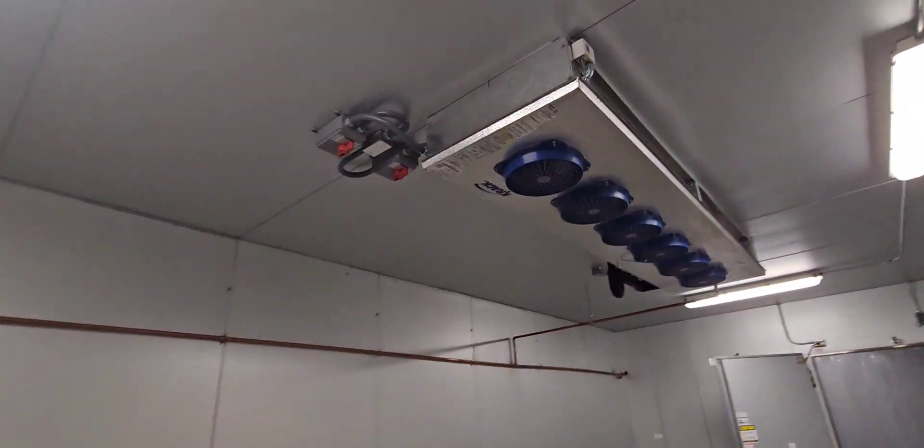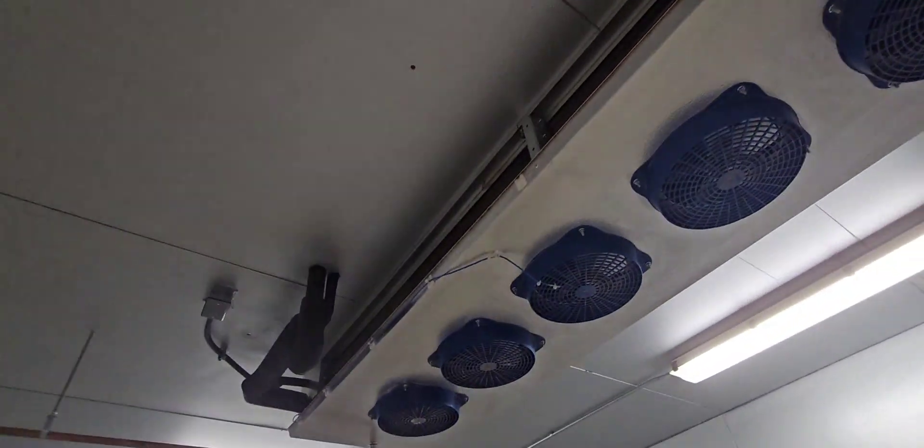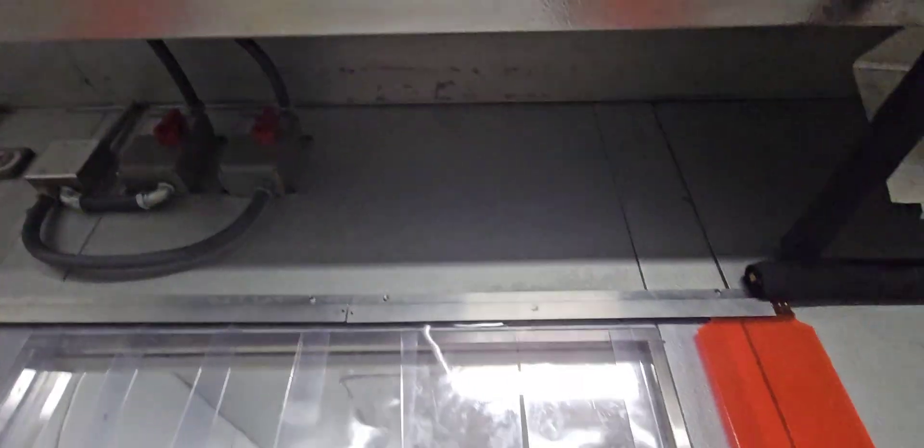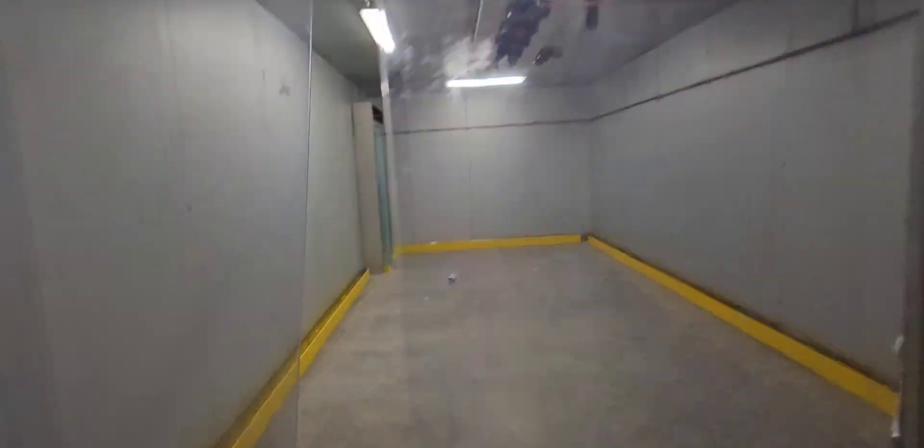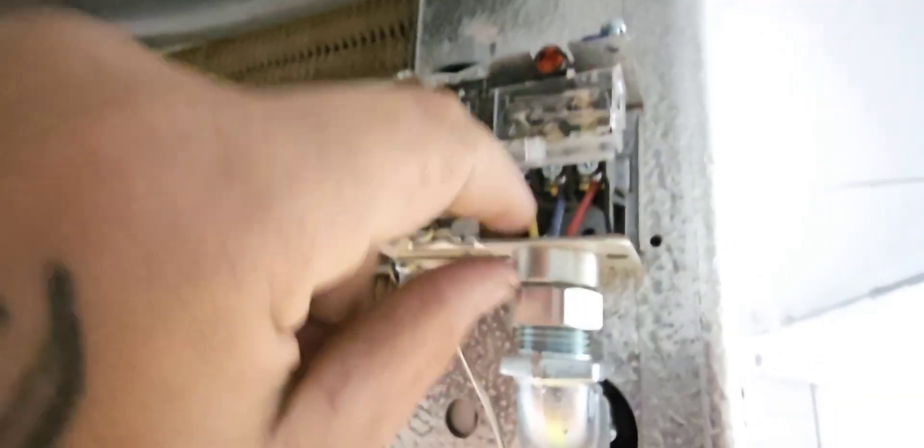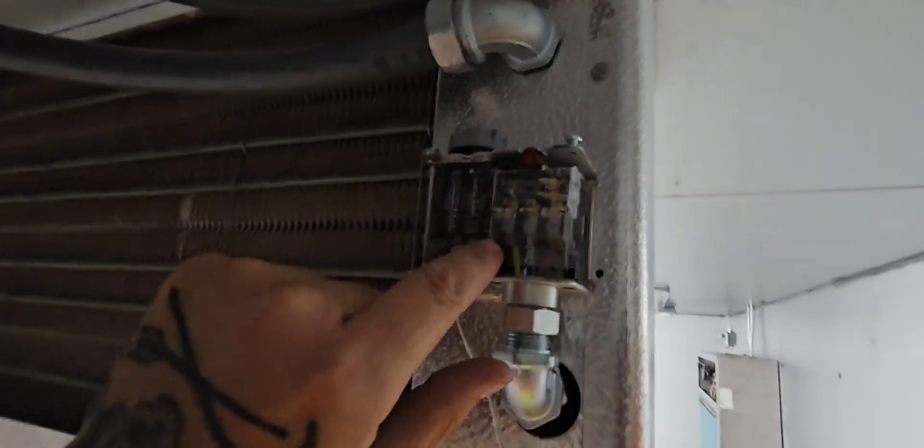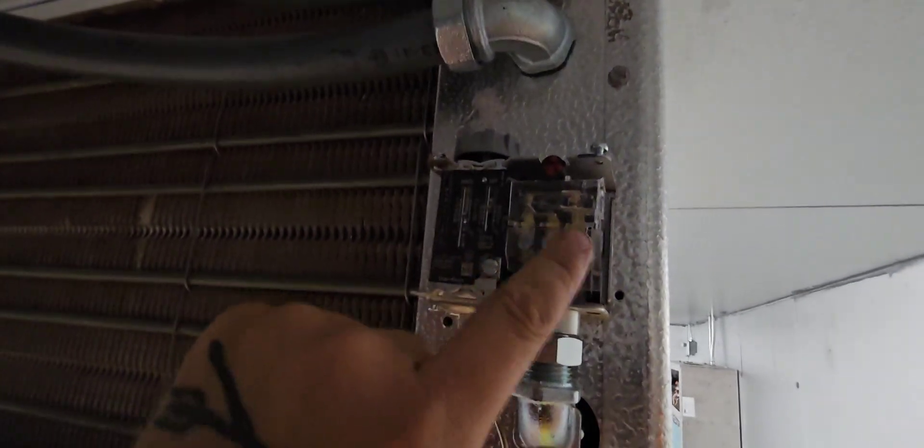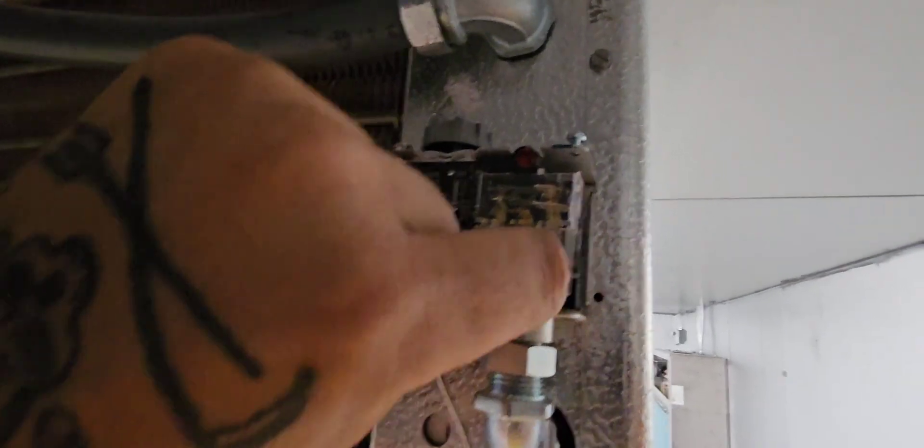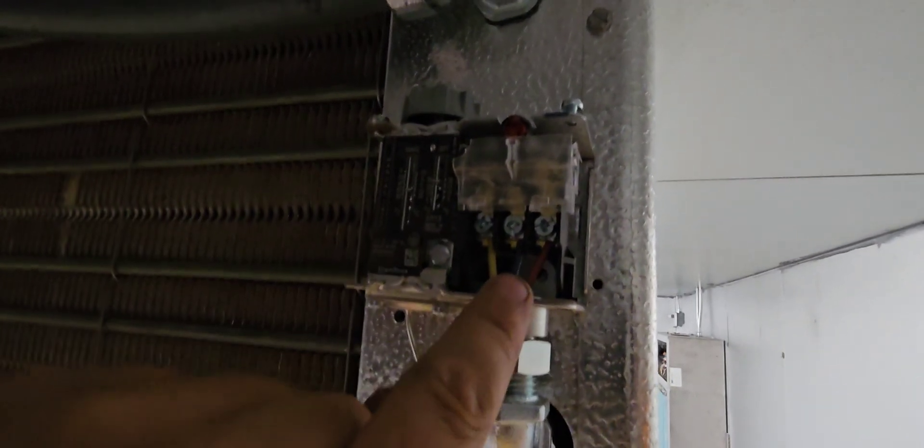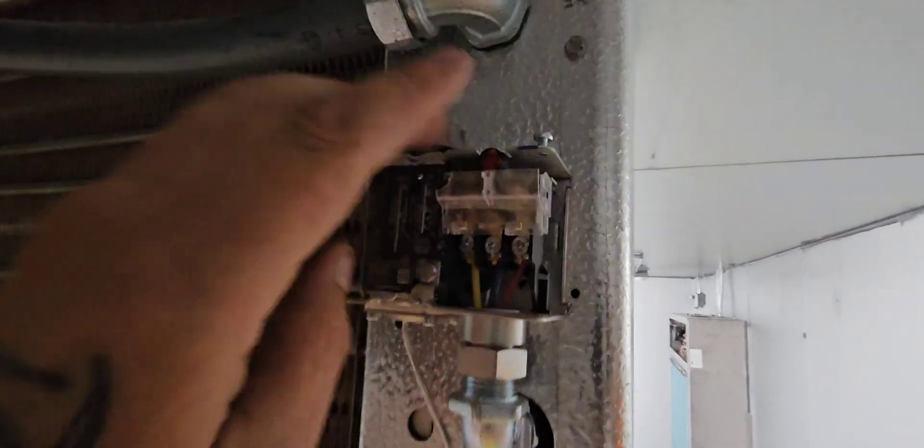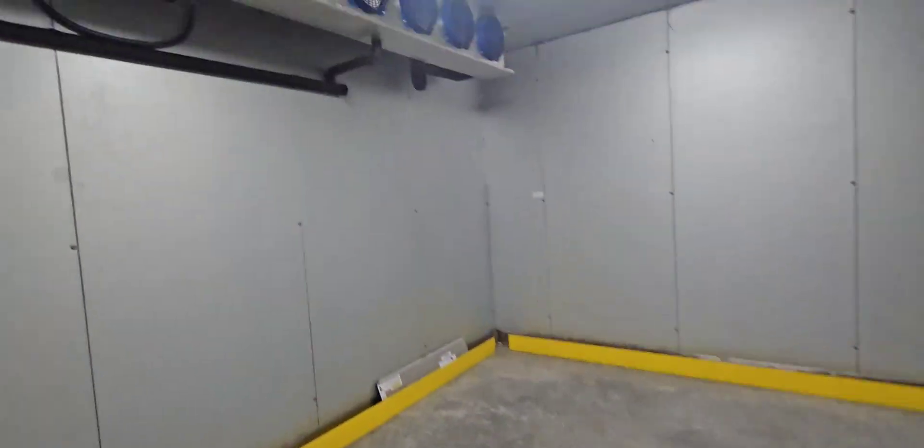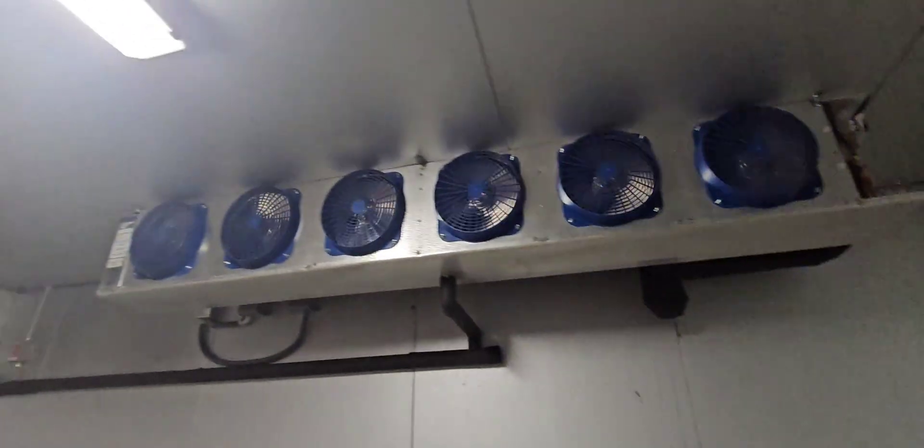In here we have for all the coils we have these breakers. Actually that freezer one we are going to need to defrost on. We got our disconnects for our fans and our heaters in here so those are already on. So once those controllers get powered up these things should be kicking on. And then the other thing we need to do is we have these fan cycle controls. Obviously the fans aren't going to run right now because it's hot. We have our one and two, one and two, so the ones are phased coming in the twos are closed. So I'm just going to jump these together right now. I just want to see these fans run, and then once we get done charging it and starting it up then I'll put that back out the way it's supposed to be and set this. Now we got fans on. All the fans are running.